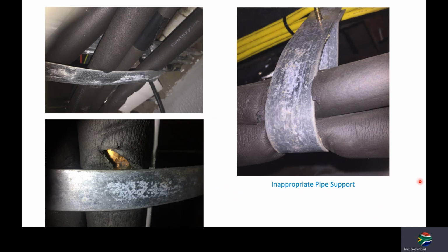Here we can see inappropriate pipe supports. You can see the insulation's already been damaged. The brackets are eventually going to cut into the softer copper and create refrigerant leaks. That is most definitely happening already. So do not use metal straps to purely support refrigerant pipework.